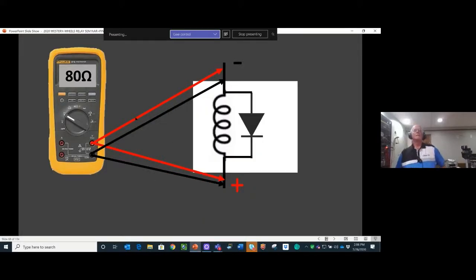Okay. The reason you can't use an ohm meter is because the diode is connected in parallel with the coil, and the diode has much higher resistance than the coil does. So even if you do hook up your ohm meter and reverse the leads, the ohm meter will read 80 ohms, or the resistance of the coil, each way. Even if the diode is there, the only way it would read different is if the diode was completely shorted as a conductor. Then the ohm meter would read 0.